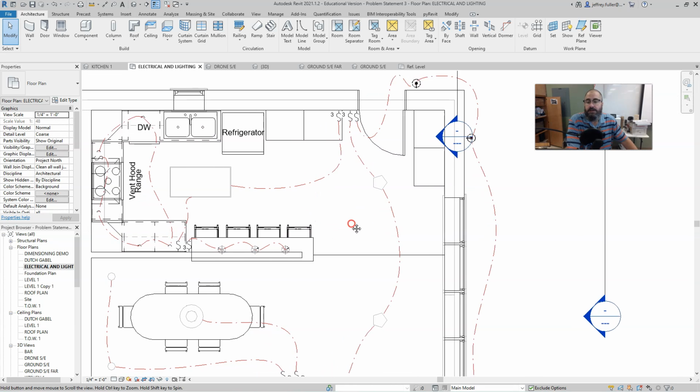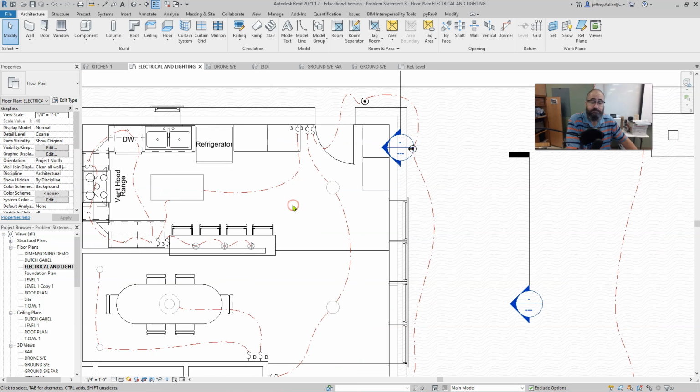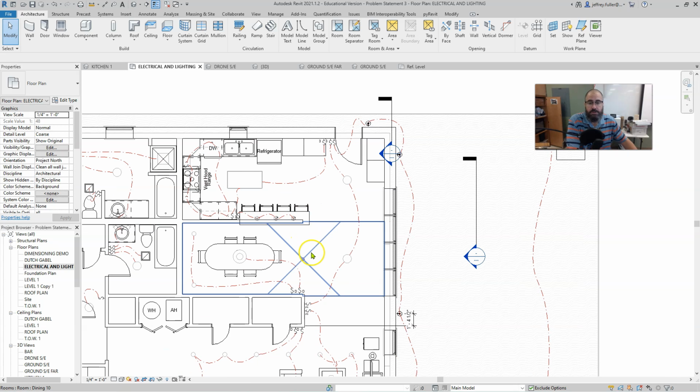Okay. And just like in this instance right here is another three-way switch for this fluorescent light fixture in the middle of the kitchen. From the switch, the wire runs to the fixture and then out of the fixture to the second switch. Now, if you have more than two switching locations, you're going to have to use a four-way switch.